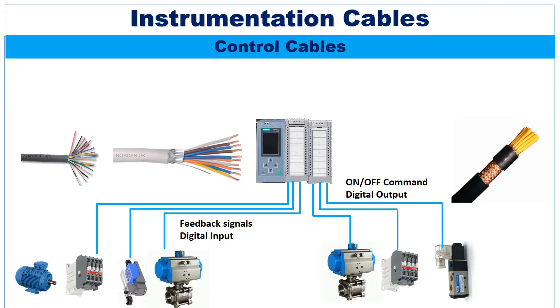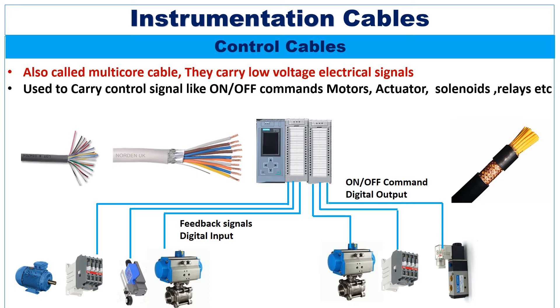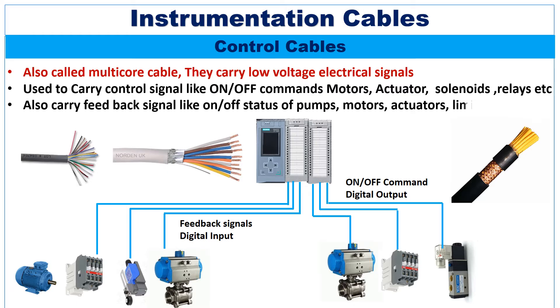Control cables are also called multi-core cables. These cables carry low-voltage electrical signals. The control cables are used to carry low-voltage control signals like on-off commands of motors, actuators, solenoids, relays, etc. These cables also carry feedback signals like on-off status of pumps, motors, actuators, limit switches, etc. Twisted cores are not required in control cables, and regular control cables do not have any shielding, though they can have shielding in some cases.